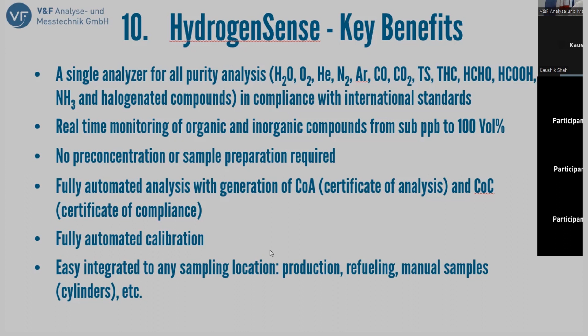All right, if we go to an installation of a device like this, there are always prerequisites. So what we are going to do is deliver you the device. We also have a smaller sample switching unit, which I will show you later on. But the prerequisites that we need, which we do not provide with the instrument, are zero and span calibration gas cylinders. This is a type of instrument that needs calibration gases in order to establish all the correct factors to do the measurement properly.